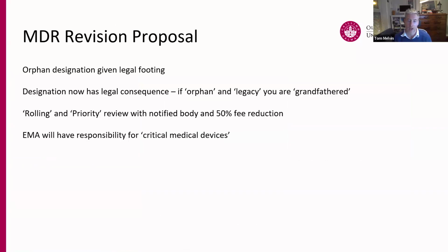Next slide, please. On the 16th of December, the European Commission published a proposal to amend the medical device regulation. What are the most important changes in that proposal? Well, firstly, orphan devices that currently have a guidance will get a designation under the regulation itself. So that's not a very big change, but the second thing on the list here could have important consequences. If you have a designation as an orphan device, and if you were a legacy device, meaning approved under the directive framework, for the first time we could have grandfathering for these devices, where they will automatically be brought in and given MDR compliance. Some other changes in the proposal relate to rolling or priority reviews with notified bodies and a proposed 50% fee reduction.